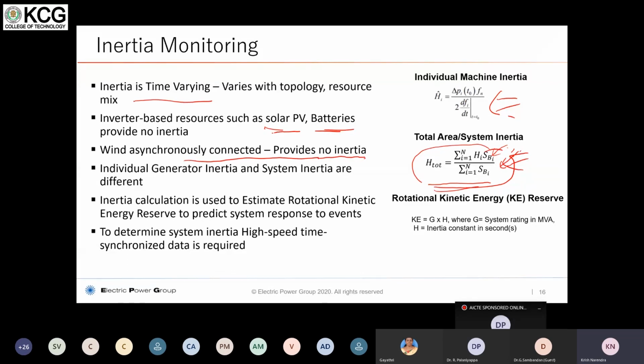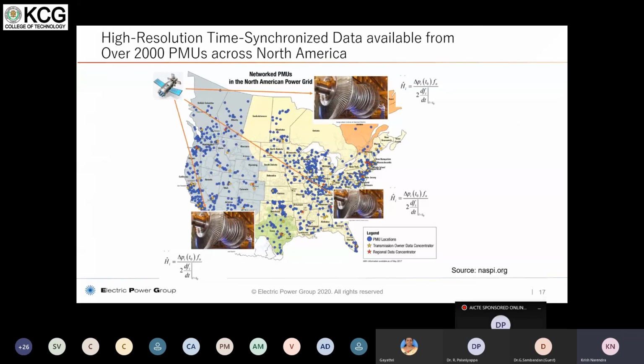Now, individual generator inertia, as I said, can remain pretty much constant because of the way the rotational mass and other things are designed. But when it comes to total system inertia and area-wise inertia, these are all variable quantities that you have to understand. That's the reason why we need to determine the system inertia with high-speed, time-synchronized data such as synchrophasors, which are highly suitable for monitoring the inertia of the system. Now, high-resolution time-synchronized data: how is it useful, and how can synchrophasor technology provide the evaluation of inertia in real time?